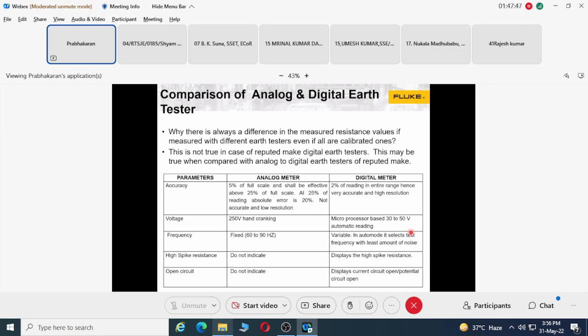Why we limit this voltage is as per IEC standards. It is actually 50 volts that is recommended for our testing, and sometimes 250 volts also. But for majority of applications, the precision of the voltage is very critical to ensure the accuracy of your measurement.